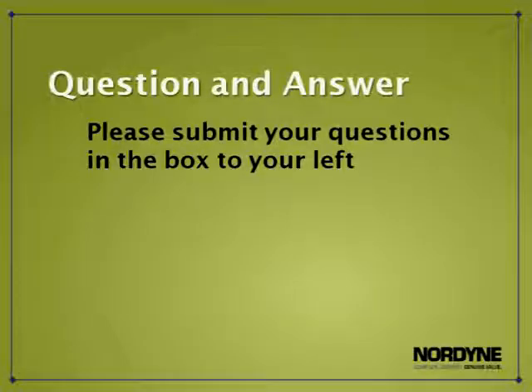Next question from Maria. Where are the limits? Are there limits on the blower housing of the gas furnaces? Maria, yes, there are. There are two limit switches on either side of the blower motor. Our limit circuit, remember, as David mentioned in the video, is all wired in series with one another. It starts out through the heat exchanger limit, down through the rollout limit, through the vent pressure switch or limit switch, and then down to the blower limits.